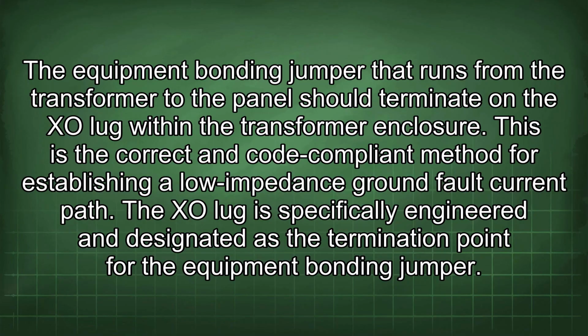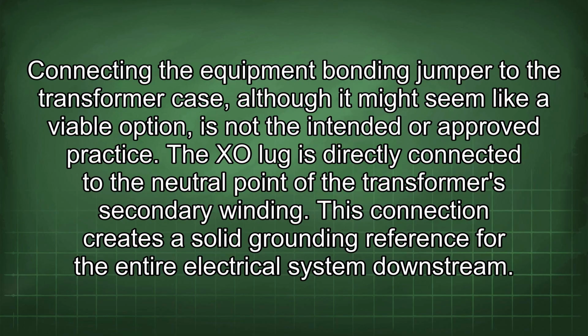The equipment bonding jumper that runs from the transformer to the panel should terminate on the XO lug within the transformer enclosure. This is the correct and code-compliant method for establishing a low-impedance ground fault current path. The XO lug is specifically engineered and designated as the termination point for the equipment bonding jumper.